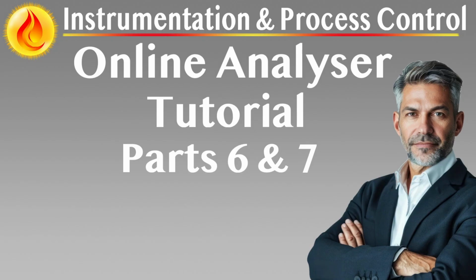Electrical facilities must comply with international standards such as IEC 60364 for low voltage installations and IEC 61010 for measurement and control equipment. Calibration gas systems. Accurate and traceable calibration is vital to analyzer performance. Calibration gases, often certified gas mixtures, must be available for periodic zero and span checks. Key system elements include high-purity gas cylinders with regulators, flow control valves and rotameters, changeover manifolds for multiple gas sources, pressure relief valves and check valves, and safe routing of calibration gas lines to the analyzer panel.